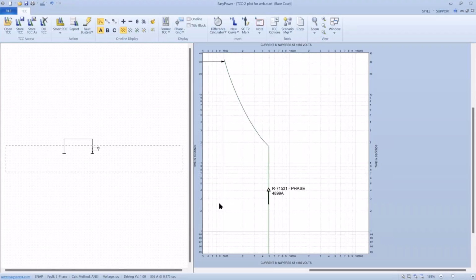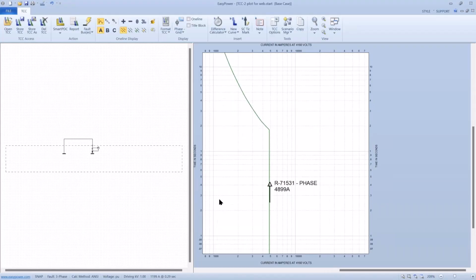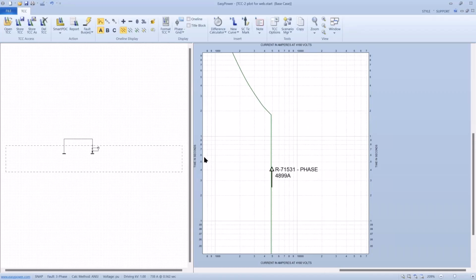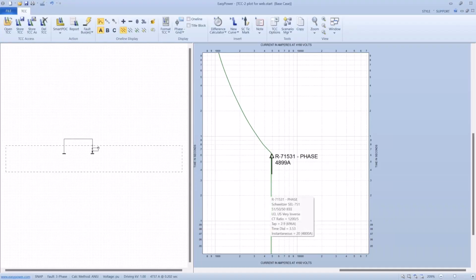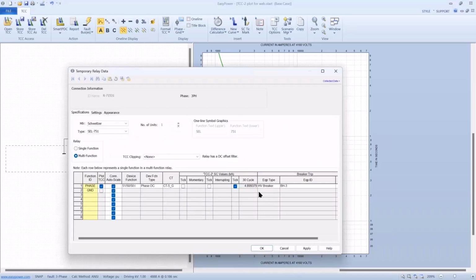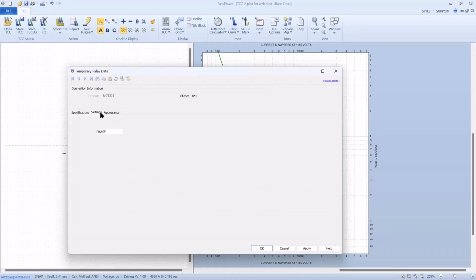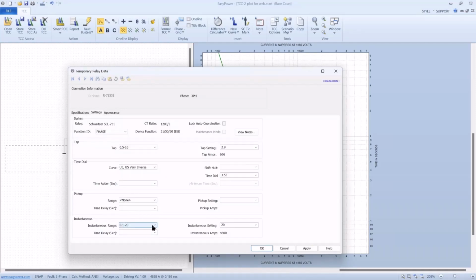and I want this to be tripping at 650 milliseconds. So if I zoom in a little bit, 650 is going to be right about here. So I'm going to take my tick mark up and look at the bottom of the cursor coordinates. So there's 575, 600 milliseconds. And I don't want that to be instantaneous. So now I can't move the instantaneous setting beyond that point. So let's go back and make an adjustment. All right, so there's no clipping. I'm not going to set my instantaneous on.